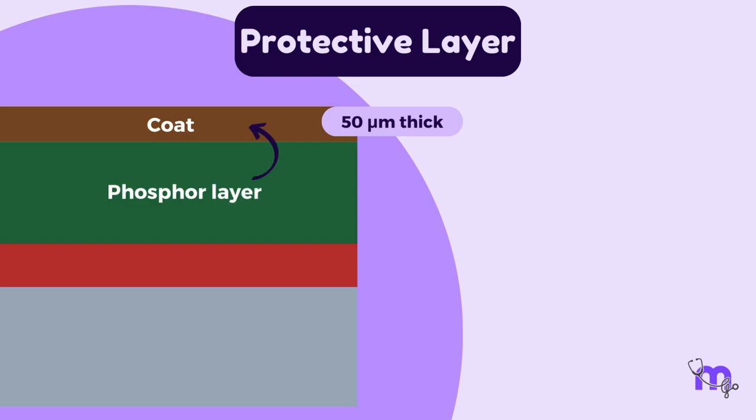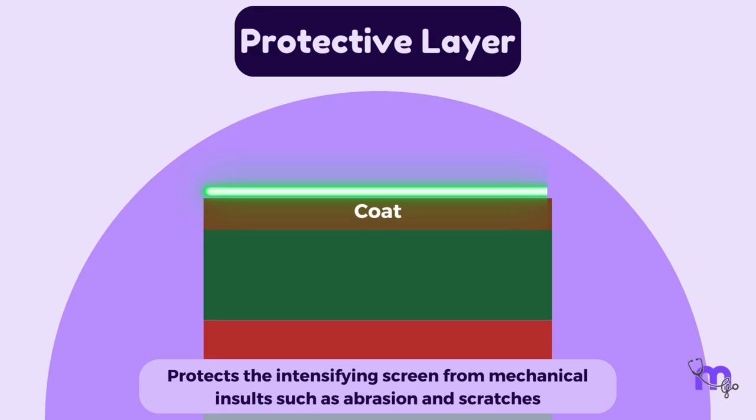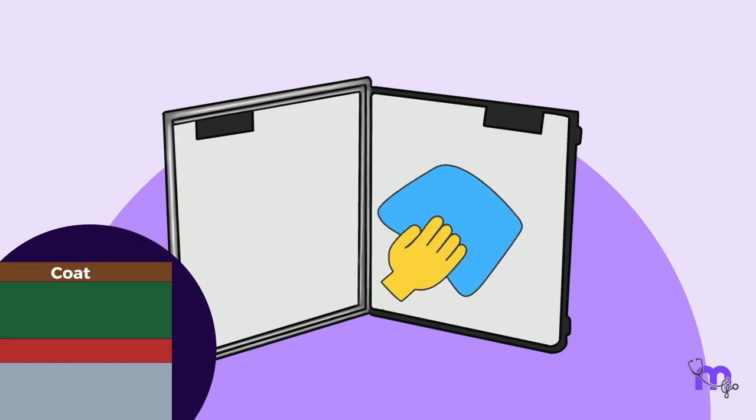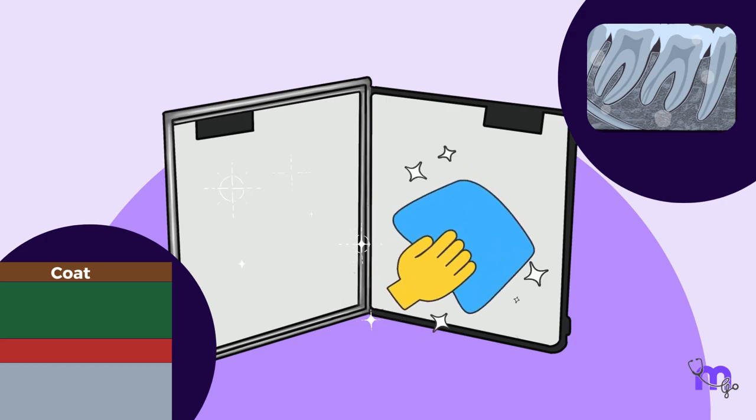The final layer is the protective coat of 50 micrometer thickness. It is placed over the phosphor layer. As the name suggests, it protects the intensifying screen from mechanical insults, such as abrasion and scratches. It is important to regularly clean the screen as debris can cause white spots on the image. Fortunately, the protective layer makes cleaning easy.